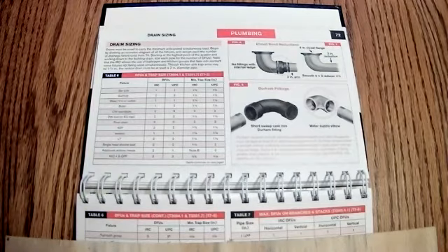Floor drains are going to have no fixture units. You'll notice they're mainly emergency floor drains, but you're going to have at least a 2-inch trap on those. They're going to run into maybe a 3-inch drain line or whatever. A kitchen sink, and there's an asterisk next to that, and I'll have to figure out what that asterisk means. Basically, 2 fixture units, again, 1.5 inches.